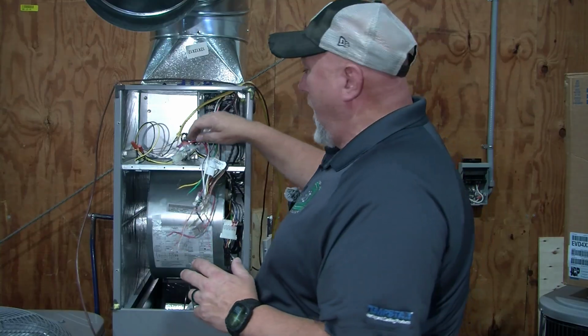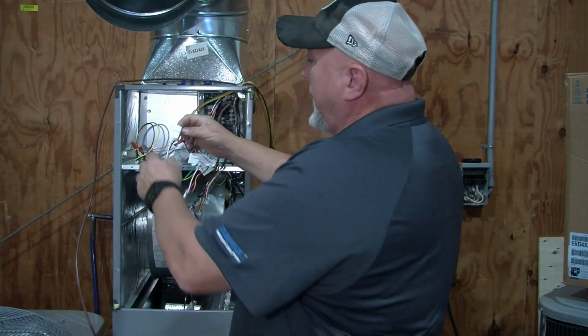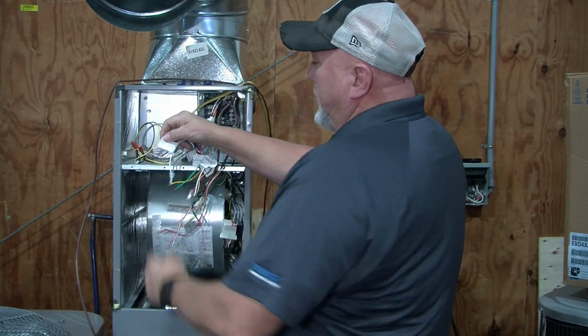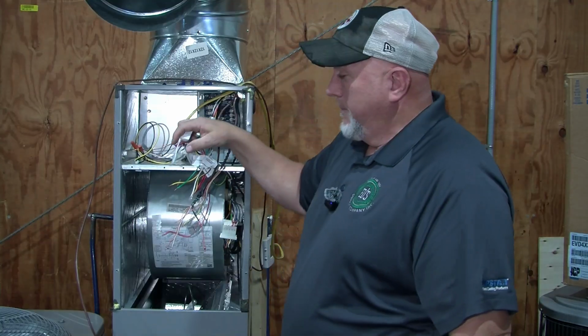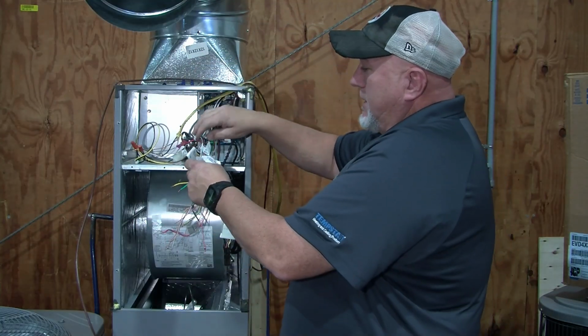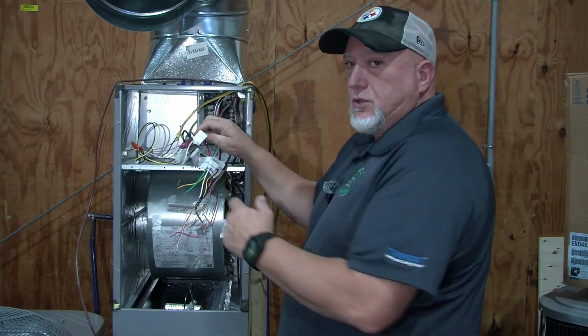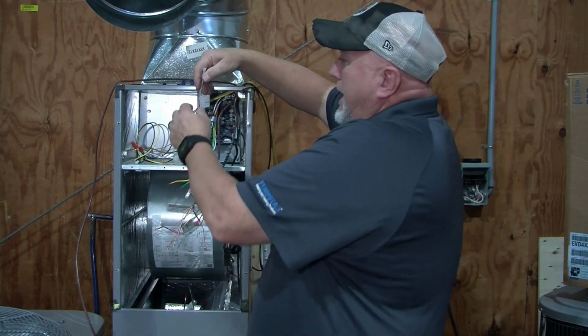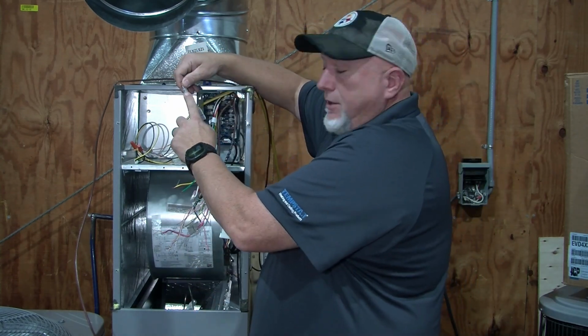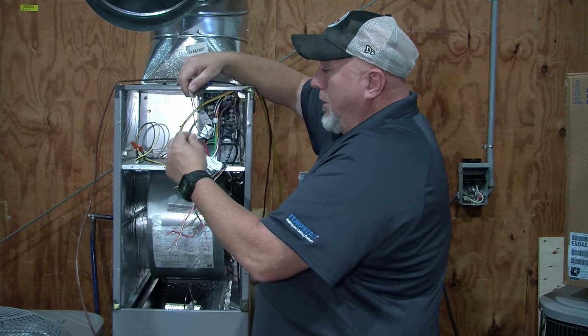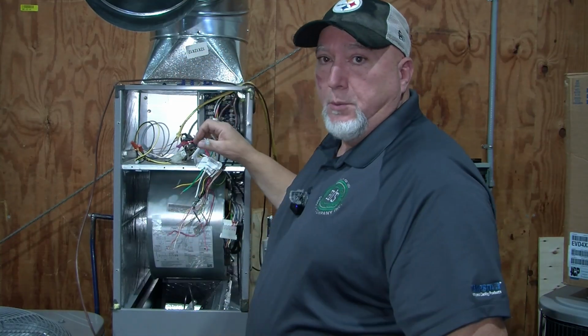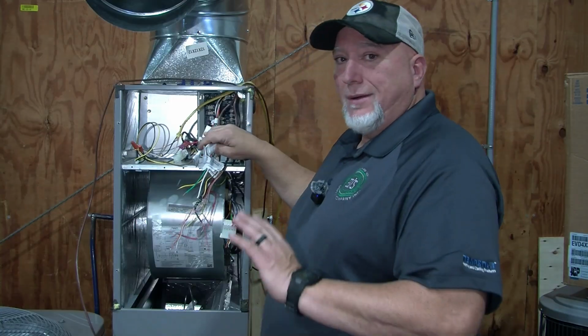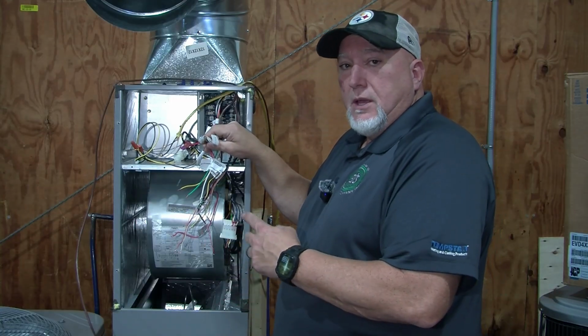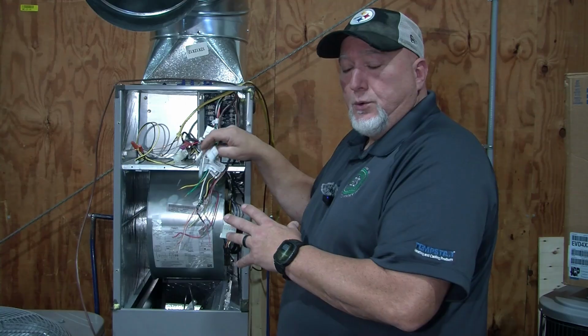Because one of the most common problems we have is this wire here, which is labeled Y out to fan coil, and a lot of people are cutting this wire because the old air handler had a pigtail that came out of this cap and had a white wire, and you would wire that to your white terminal on your thermostat. Well, you don't have to do none of that on this model, so that's why we're going to go through this and show you this.